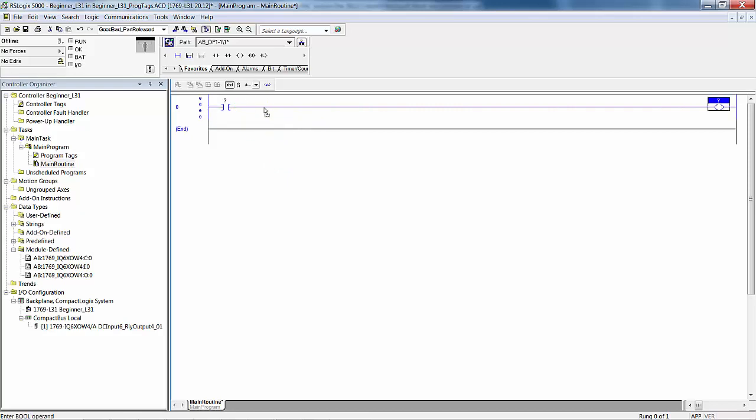This is where we wanted to put it. Anyway, I'm going to delete that and do that over like we did. So you see that green Mimi there? As long as you see that green Mimi, you can let go, and that's where it will attach. But because this is a read-only type instruction here, and this is an execute or an action instruction, the action instructions are always going to go all the way to the right, whereas the read type instructions are going to go all the way to the left.